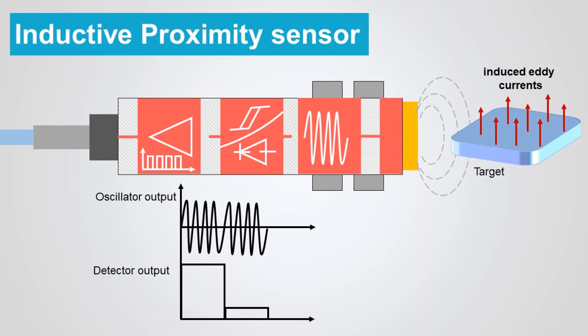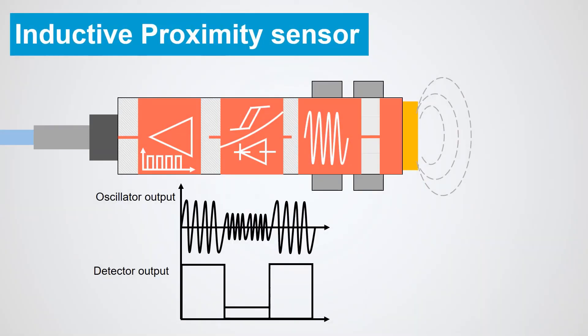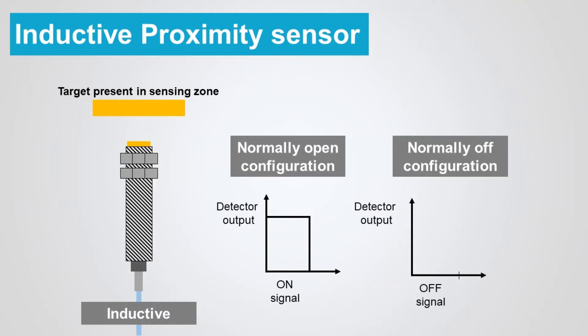When the target finally moves from the sensor's range, the circuit begins to oscillate again, and the Schmitt trigger returns the sensor to its previous output. If the inductive proximity sensor has a normally open configuration, its output is an on-signal when the target enters the sensing zone. With normally closed, its output is an off-signal with the target present.